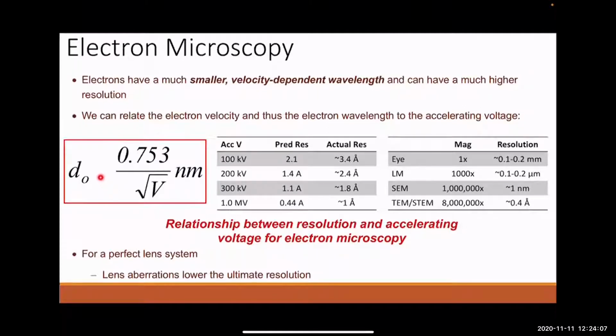Again, I can see my equation didn't quite show up. Hopefully it's correct on the slides. There should be an equal sign here and an alpha, that half cone angle here. But you'll notice the V is the voltage. And on any electron microscope, you'll see one of the primary controls or knobs on the microscope will be the accelerating voltage. And that's directly related to setting the electron wavelength.